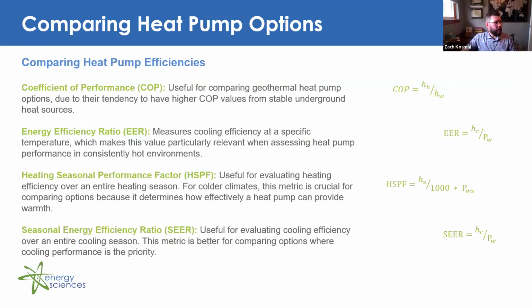So, moving on, going back to our heat pump efficiency metrics. Your coefficient of performance, as a reminder, this is your heat produced in BTU per hour divided by your equivalent electric input energy, also in BTU per hour or kilowatt hours. This is useful for comparing geothermal heat pump options. This is because of their tendency to have a higher COP value from that stable ground temperature heat source.